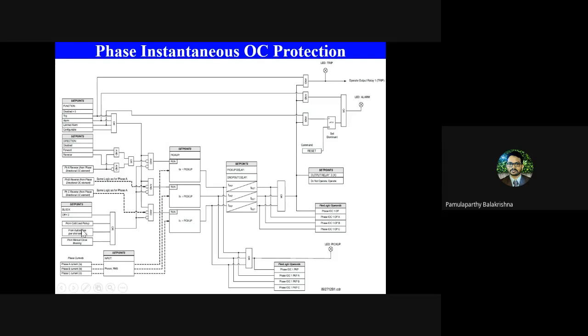The second one is the auto reclose, which you might have heard of. Auto reclosing is an action by the breaker where it checks whether the fault is permanent or temporary. For example, there is an overcurrent condition and the breaker has tripped. It has to check whether it's a temporary fault or a permanent fault. If it's a temporary fault, it will die down in a few milliseconds. So the auto recloser operates the breaker on and off 3 to 4 times just to ensure whether it is a temporary fault or a permanent fault. Once it confirms that it's a permanent fault, only then will it execute the action.